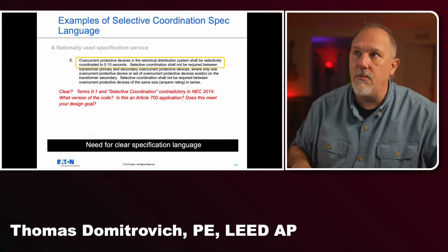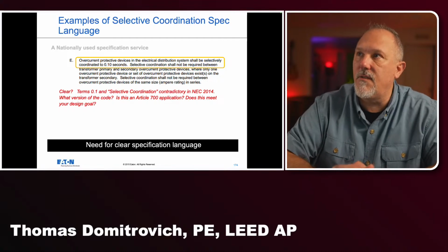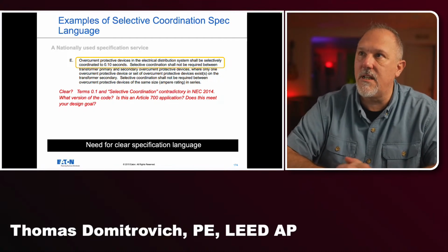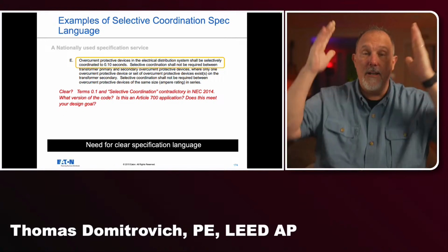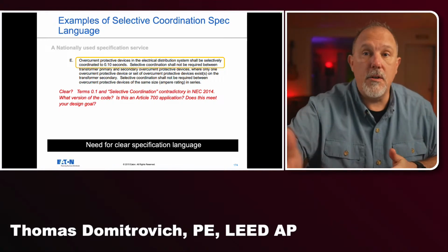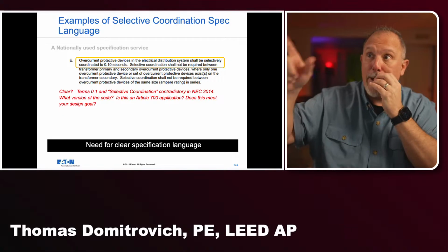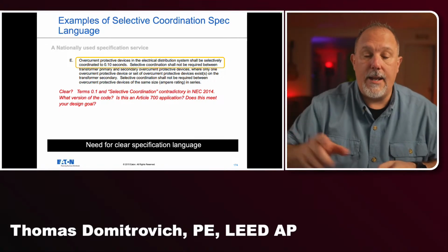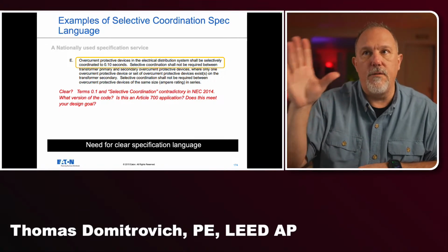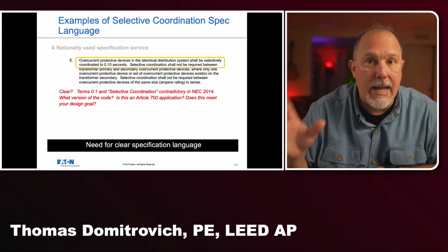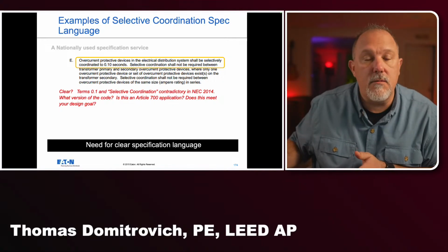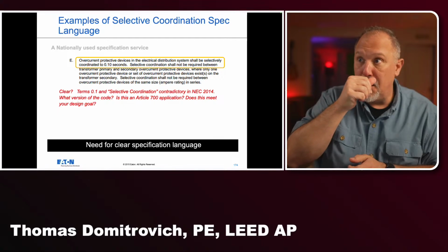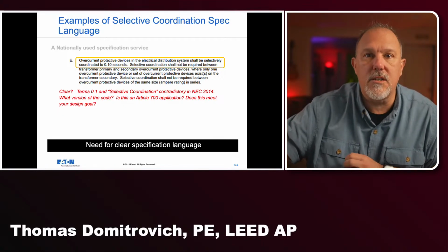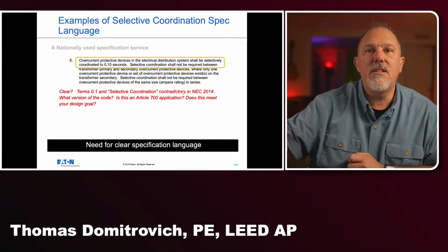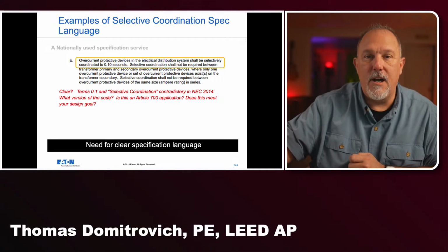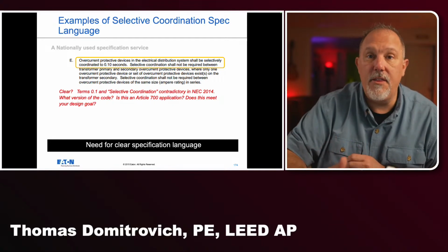Don't use that language. Here's another one. Overcurrent protective devices in electrical distribution systems shall be selectively coordinated to 0.1 seconds. 0.1 seconds is coordination. It's not selective coordination. This is where it starts. And I don't know if inspectors get to review the spec language that the design was made towards, but this is a good place to start to say, what was asked of whoever was providing the quote?